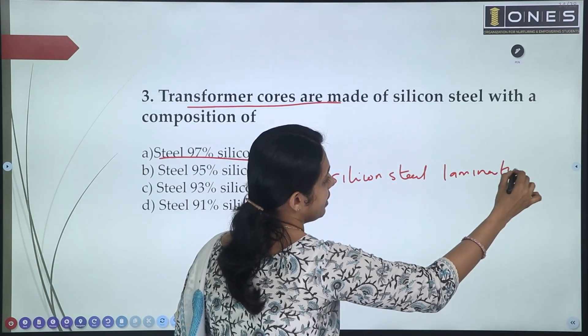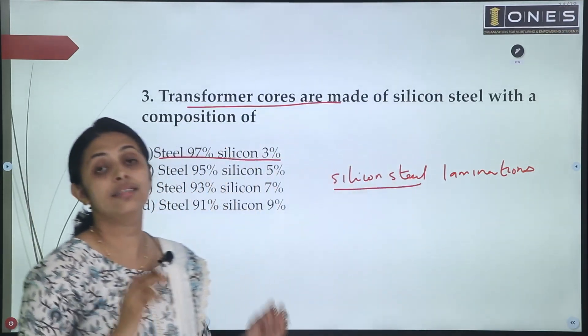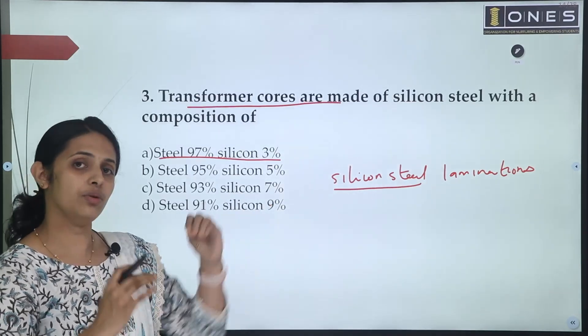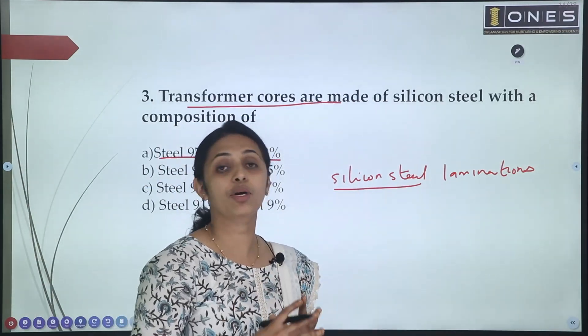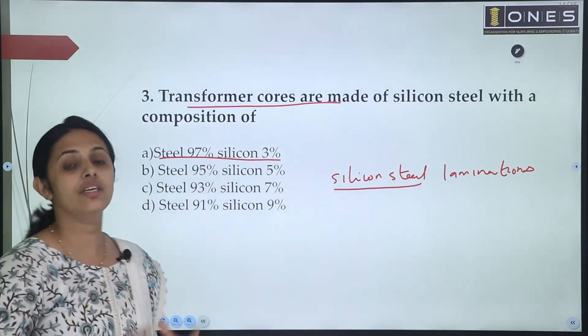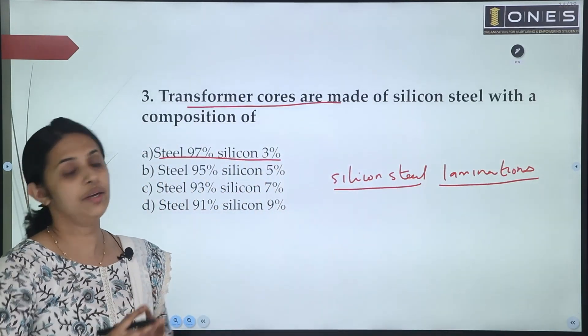If we are using the transformer core, we use silicon steel laminations. We usually use 3 to 5% silicon. Adding silicon reduces hysteresis losses by improving the BH curve. Using laminations reduces eddy current losses. So for transformer cores, silicon steel laminations are used to reduce both hysteresis and eddy current losses.